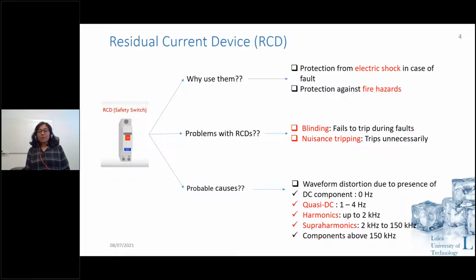What are the probable causes that can occur? A lot of work has been done on recognizing some of the reasons why these two can happen, and it mainly deals with the waveform distortion that we see. I have categorized them according to the frequency range, like the DC component. Basically, the presence of DC in the leakage current can cause blinding of RCDs, because they get saturation. We'll see the schematic of the RCD in the next slide.